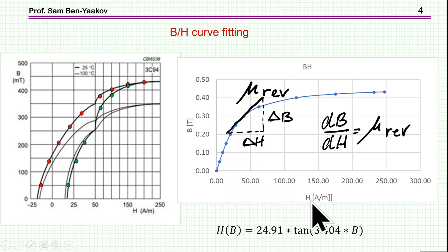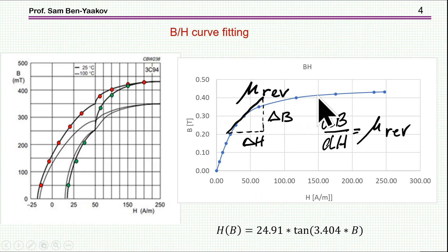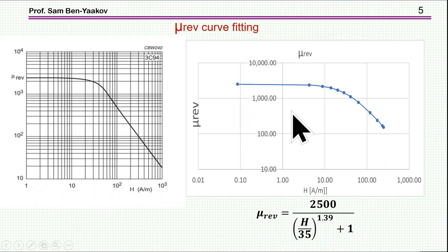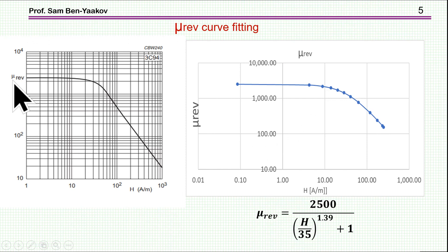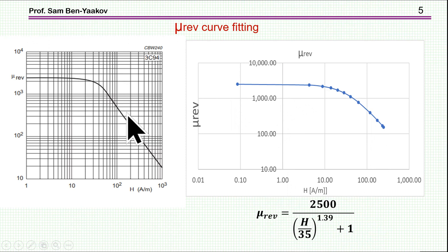As we go up with the H magnetic field, the slope is changing, and this is the reason why the inductor will change its inductance as we bias it with the DC current. Another piece of information that vendors typically provide is this reversible small-signal relative magnetic permeability. Here is the data and here is the fitting, which comes to an expression that provides a pretty good fit in the region we are interested in.